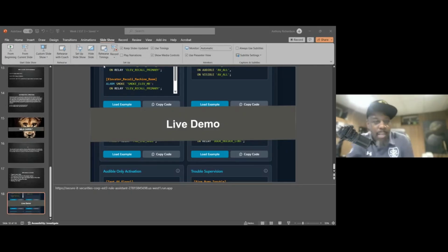So the object label text is pretty much already defined. So when I come to the rules, edit rules. Level 1, I can't make this any bigger. So we have level 1, smoke 1. Actually, this would only set off 1 smoke detector, to tell you the truth. So I will have to put the wildcard star in order to make this go active.